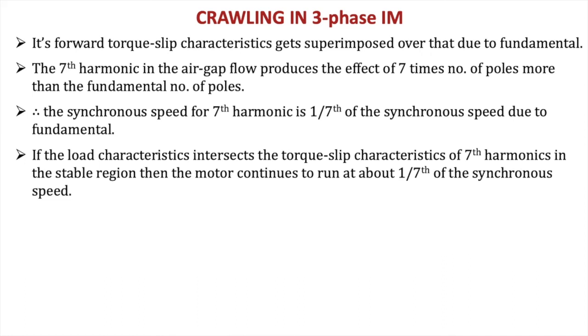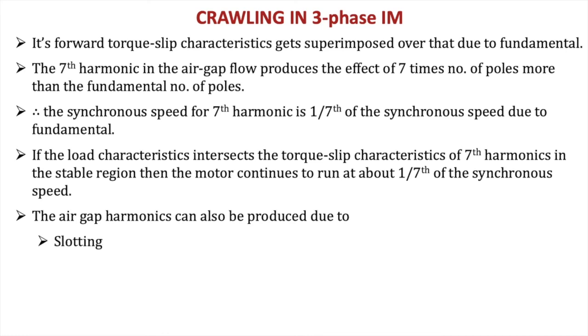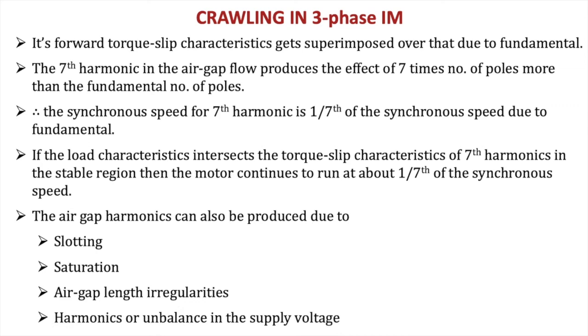So if the load characteristic intersects the torque slip characteristic of the 7th harmonic in the stable region of the given motor, then the motor continues to run at 1/7 of its synchronous speed. It's not necessary that this is the only reason for air gap harmonics. There can be other reasons, that is the slotting of the motor, the saturation, the air gap length irregularities, and the harmonics or unbalance in the supply voltage itself. So there are many other reasons also, but mainly it is the seventh harmonic which affects, because it has the maximum magnitude and it is in the same direction as the fundamental. Hence the seventh harmonic gets superimposed on the fundamental, and if the load torque is cutting the speed torque characteristic in the stable region, then the motor will continue to rotate at this lesser speed.